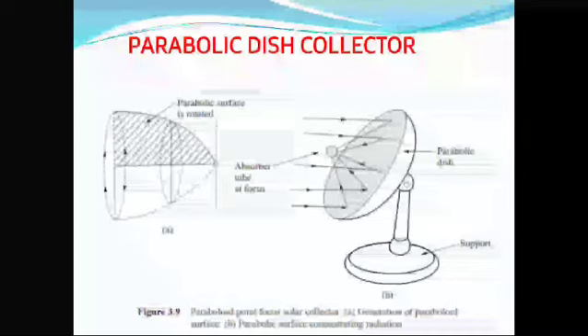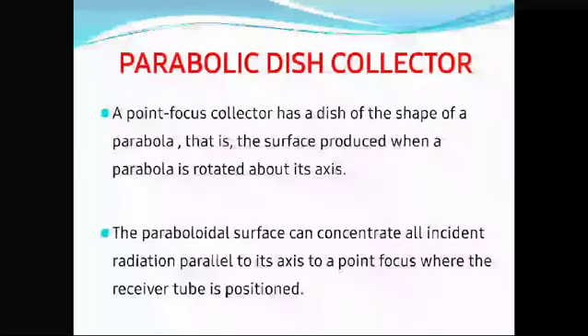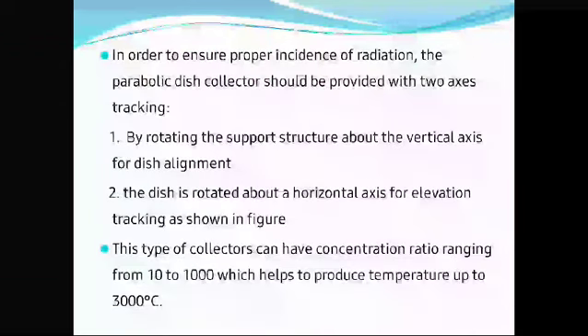The second type is the parabolic dish collector. A point-focused collector has a dish in the shape of a paraboloid, which is a surface produced when a parabola is rotated about its axis. The paraboloidal surface can concentrate all incident radiation parallel to its axis to a point focus where the receiver is positioned. In order to ensure proper incidence of radiation, the parabolic dish collector should be provided with two-axis tracking.